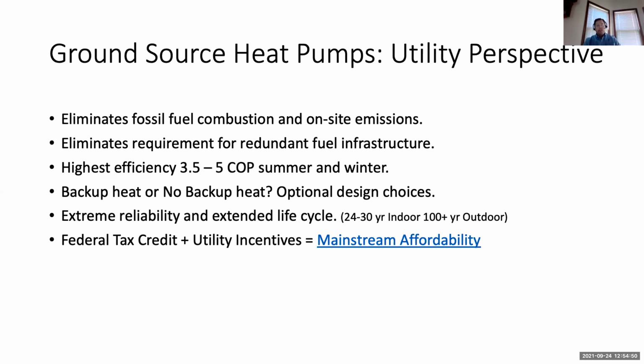So first of all, from the utility perspective, I am talking specifically of ground source heat pumps. They do eliminate fossil fuel combustion on site. They eliminate the need for redundant infrastructure—by that I mean delivery of natural gas systems and/or other delivery. They offer the highest efficiencies, up to 500% efficiency in heating mode, and the highest efficiencies in cooling mode as well. You can have backup heat if you choose to.